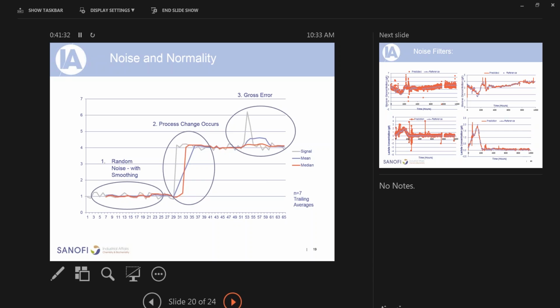I added a data point that was clearly not part of the other data set — a gross error, enormously different. If that were to happen with your spectrometer in a manufacturing process, that value would get stuck within the mean signal for a while afterwards. If you look at the blue line, you're stuck with an offset for a little while until you've moved a sufficient distance from the gross error, and then you're back at the set point. The median, on the other hand, doesn't even see the gross error — it just ignores it entirely.